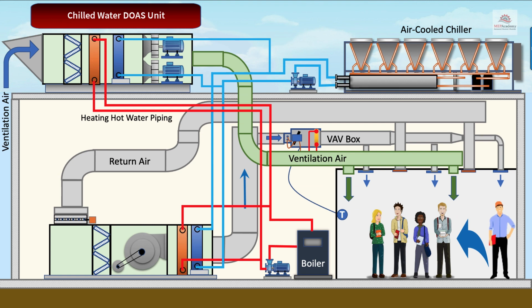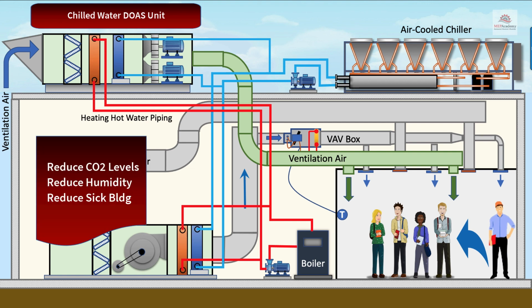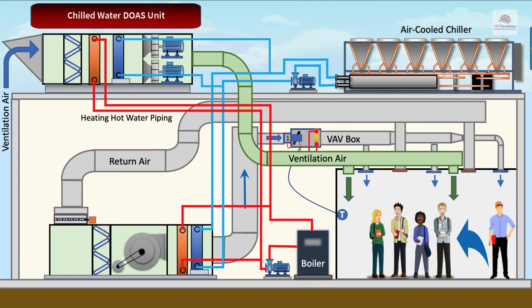One of the main differences between this chilled water DOAS unit and the DX DOAS unit is in the method they produce dehumidification and cool air. The DOAS unit will reduce indoor CO2 levels while removing excess humidity and condensation, which reduces sick building syndrome. The DOAS doesn't recirculate indoor air back through the unit, so the air is always fresh. That is, if the outdoor air is better than the indoor air.